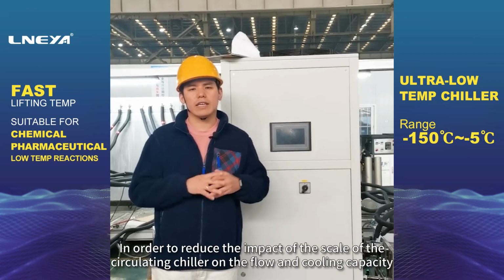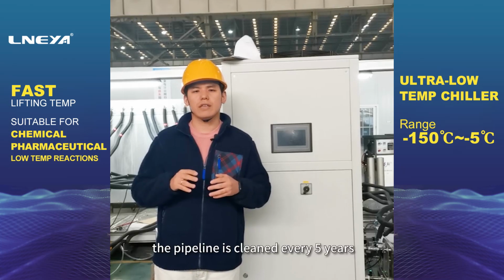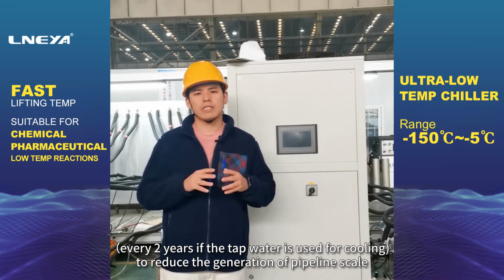In order to reduce the impact of the scale of the circulating chiller on the flow and cooling capacity, the pipeline is cleaned every 5 years, or every 2 years if tap water is used for cooling, to reduce the generation of pipeline scale.